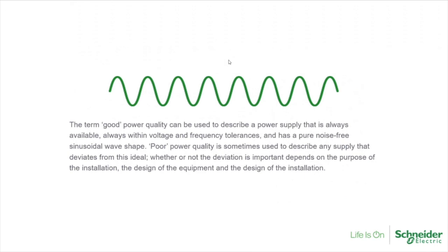Passive equipment is kind of like a cap bank. When the power factor gets too low, you can throw in a cap bank. It'll bring your power factor up and keep your real power closer to your demand. Active filters are something like AccuSine that we sell, and AccuSine actually does power factor and harmonics. It can give you some ride-through on voltage variations. The idea is that it's working in real time. It's not waiting for a set condition and then it activates. As your load changes cycle by cycle, second by second, it is working to ensure that your power is reliable.